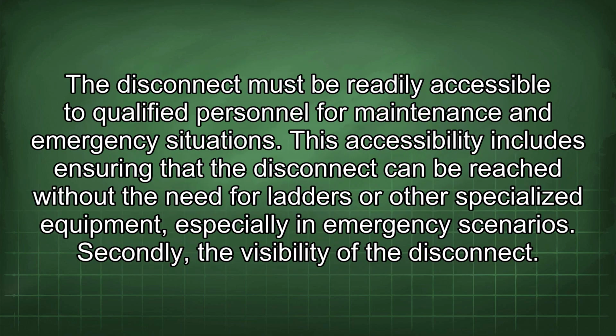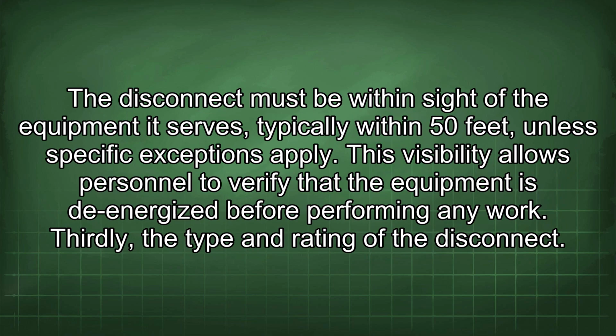The disconnect must be readily accessible to qualified personnel for maintenance and emergency situations. This accessibility includes ensuring that the disconnect can be reached without the need for ladders or other specialized equipment, especially in emergency scenarios. Secondly, the visibility of the disconnect. The disconnect must be within sight of the equipment it serves, typically within 50 feet, unless specific exceptions apply. This visibility allows personnel to verify that the equipment is de-energized before performing any work.